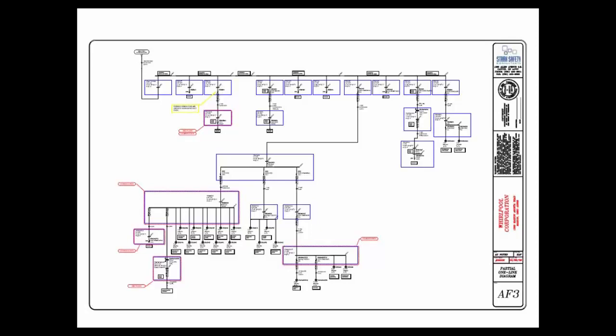Compared to an arc flash analysis diagram generated from EasyPower, here we have a lot more detail, a lot more information, a lot more depth that we need to have, such as fuse information, size, wire length, conduit — all that information. There's a big difference, so we need to make sure we have that information.